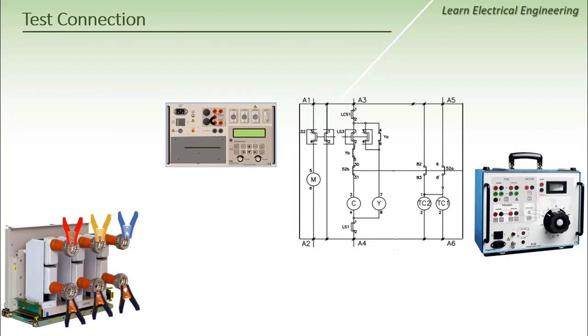Through the control supply voltage, I can supply 3 circuits specific to the circuit breaker. The first circuit I have is the charging motor circuit, and this is the motor responsible for charging the spring specific to the circuit breaker. The second circuit I have is the closing circuit, and I connect the close coil to it. The third circuit I have is the tripping circuit, and I connect the trip coil to it. Here, the control supply voltage will be used with the commands that will go to the close coil and the trip coil, based on the operation sequence that we will execute.